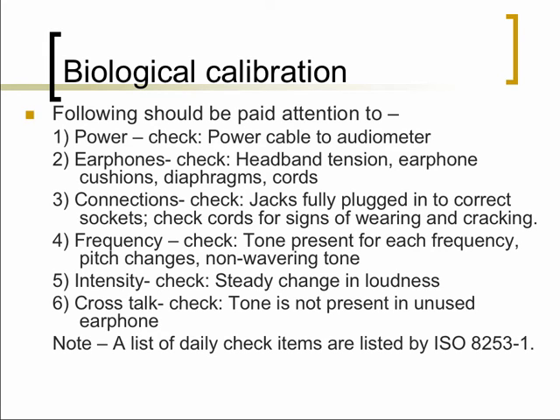The following also should be attended to. So you want to check power, you want to check the earphones, you want to check the connections if they're fully plugged in. Of course, you'll do a frequency check, an intensity check, and you want to check if there's any tone in the untested earphone or insert earphone.